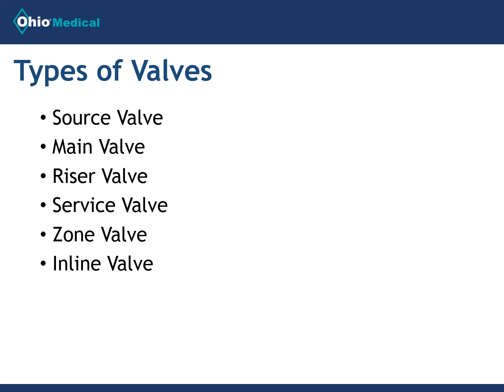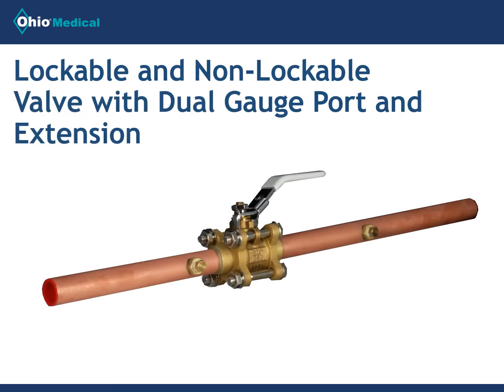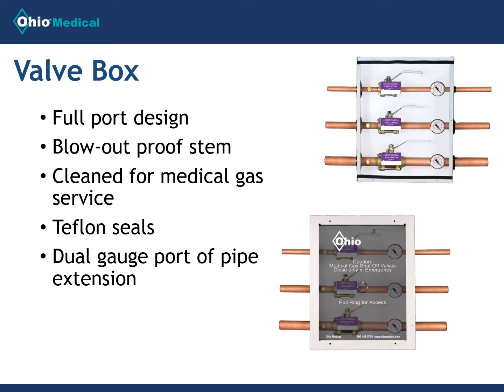Ohio Medical provides medical gas valves for all major requirements and uses within a medical or lab facility. We keep many in stock for quick delivery. All of our valves are available in lockable or non-lockable versions with dual gauge ports and extensions. They are of the full port design with blowout-proof stems and Teflon seats. All valves are oxygen cleaned. Complete valve boxes are offered with a variety of valve size combinations. Up to 5 valves can be fitted into a single box.